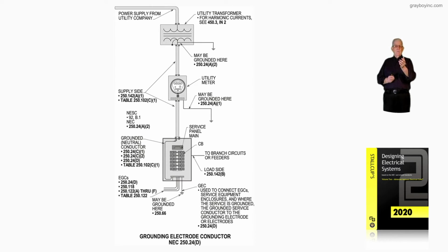And for example, the grounded neutral conductor, 250.24(C)(1), you've got to ground it there at the service. 250.24(C)(2), you've got to ground it at the service and at the transformer, and 250.24(A)(2). 250.24(D), as in dog, then you're looking at further grounding rules. That's important. And then your table 250.102(C)(1) deals with sizing the grounding conductor, as we previously pointed out, to serve as an effective ground fault path. But what I'm pointing out, if you want to focus just on that grounding conductor, there's your sections.